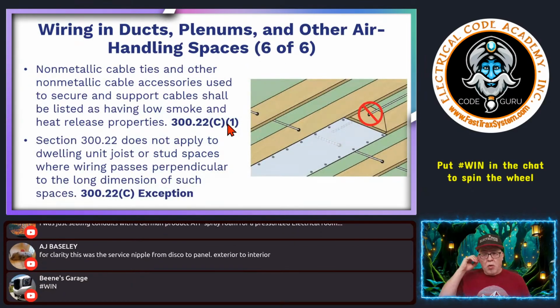Now, what about in a dwelling application? Another thing to mention is non-metallic cable ties and other non-metallic cable accessories used to secure and support cables shall be listed having low smoke and low heat release properties. That's 300.22(C)(1). So whatever you use to support cables, even MC that's allowed up there, if you use tie wraps as securing or supporting methods, they have to be low smoke, low heat release. You'll look at the markings to determine whether or not they are. You can't just go down to Harbor Freight and buy a bunch of tie wraps and use them in those spaces.